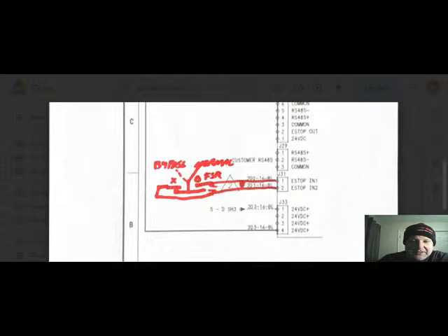Again, this would be just a little 2-position switch. Cut it into the door, mount it on the wall, wherever you want to put it. It doesn't necessarily have to be even local to the compressor room. This could be something that's tied into the DCS or the building automation system or something like that, where the operator hits a bypass button on their screen, and then it just maintains this latch while the fire suppression system is doing what it's doing, and it doesn't interrupt the compressor.